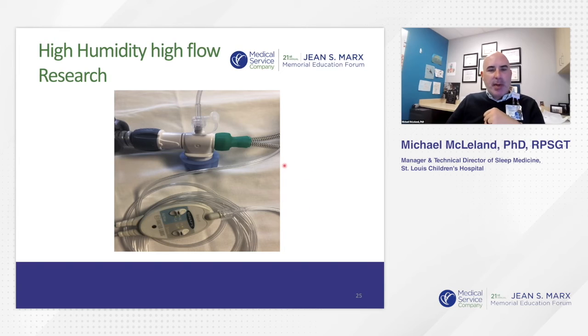Here's a picture of the actual setup. We have the T-tube, here's the nasal cannula for the high flow, and this is the tubing or circuit that connects to the Fisher and Paykel AIRVO. In between the two we have the T valve with the sample line, and then our pressure transducer, the device measuring the pressure, connected to the sleep system to collect the data.